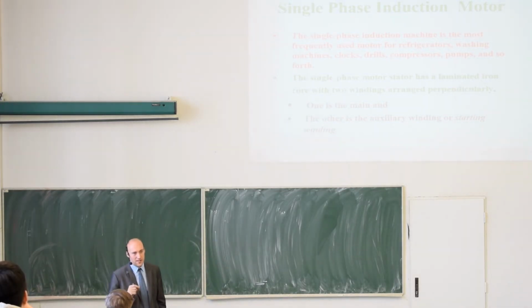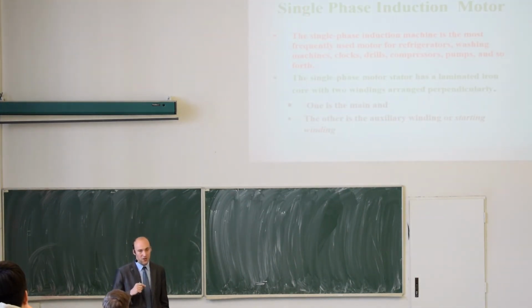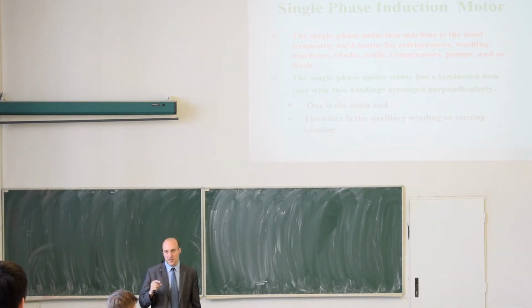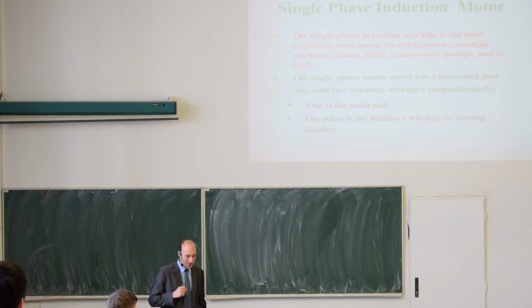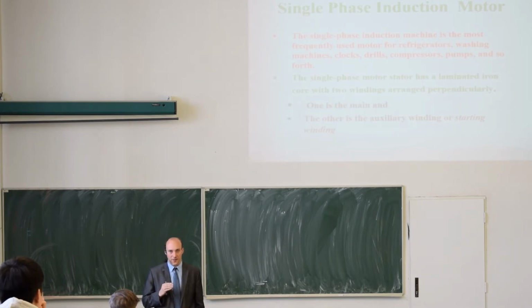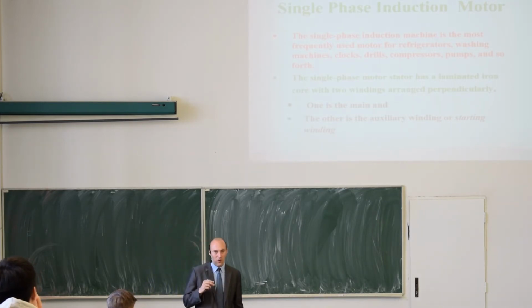The construction of a single-phase induction motor is very, very similar to a three-phase induction motor. We will see that basically there is only one difference that distinguishes three-phase motors and single-phase motors. The single-phase motor is basically a two-phase machine. The name single-phase motor would probably imply that you have only one winding in the stator, but it would not work with just one winding. If you run a three-phase motor only on two phases, you will have a similar problem as with a single-phase induction motor, that it will not be able to start without external help.